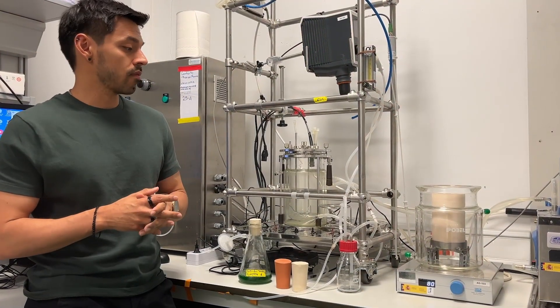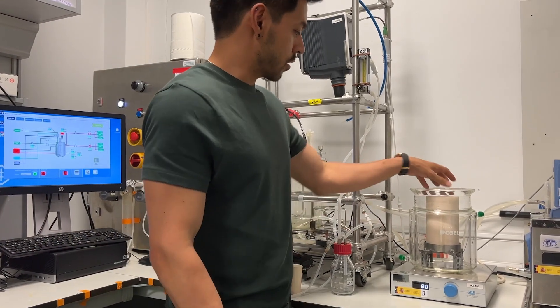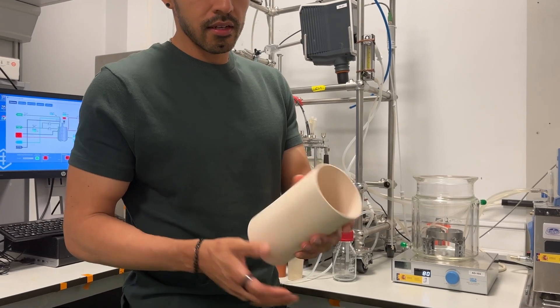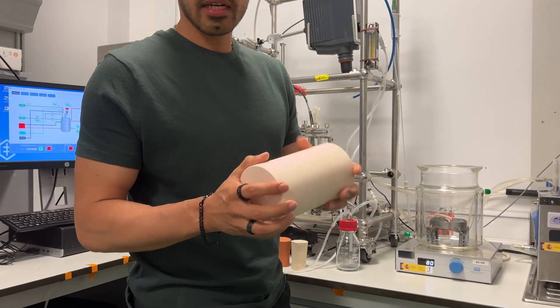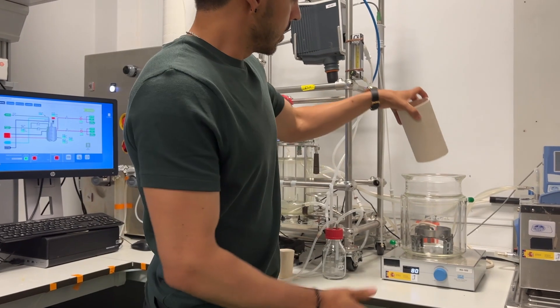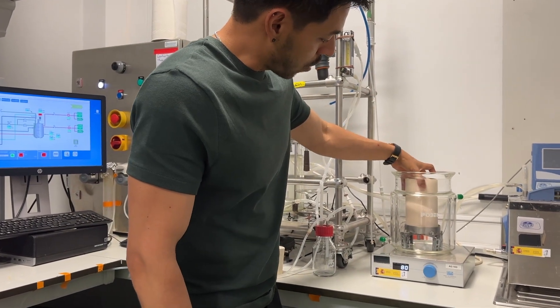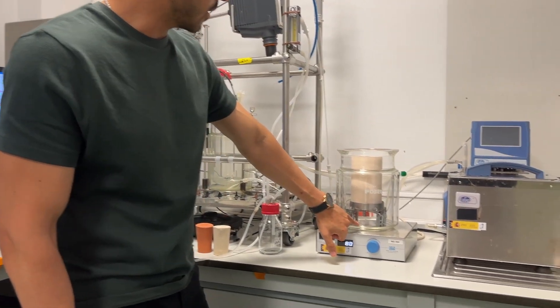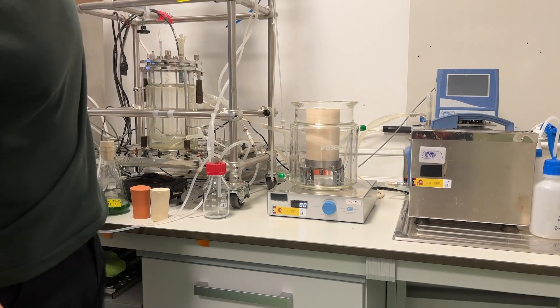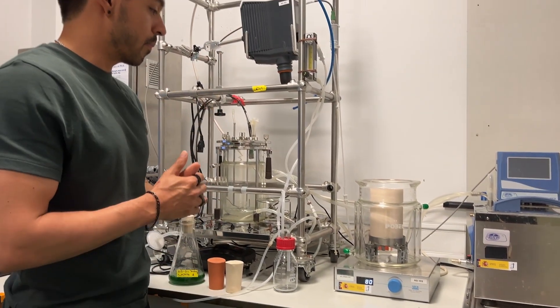When we want to implement the two-liter multi-chamber bioreactor, we use this setup. Here you can see the 800 mL ceramics — it's the same type of ceramic as the one used in the bioreactor for filtering. We place this in the holder, and you can see the magnetic stirrer in the outer chamber, while the inner chamber is mixed by a standard impeller.